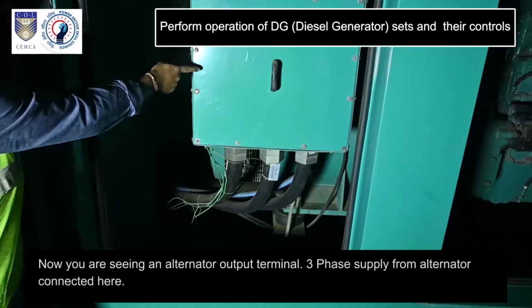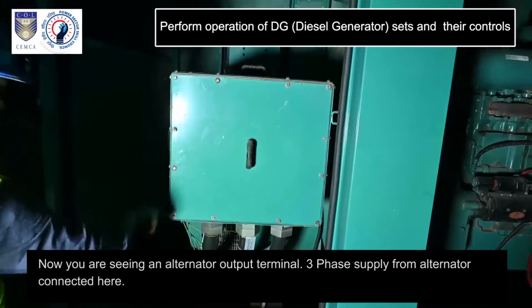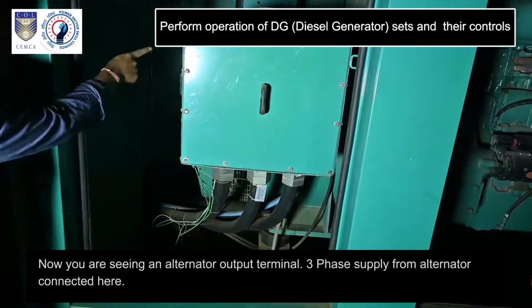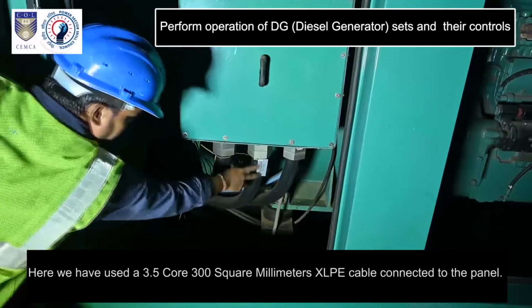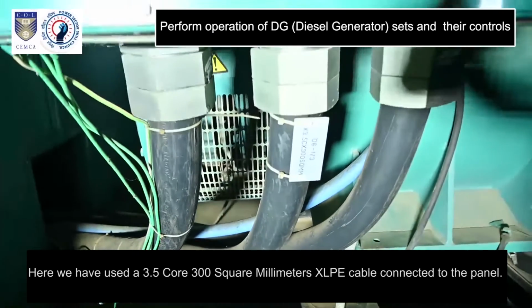Now you are seeing an alternator output terminal. The 3-phase supply from the alternator is connected here. Here we have used a 3.5 core 300 square millimeter XLPE cable connected to the panel.